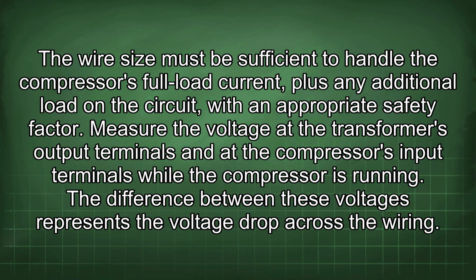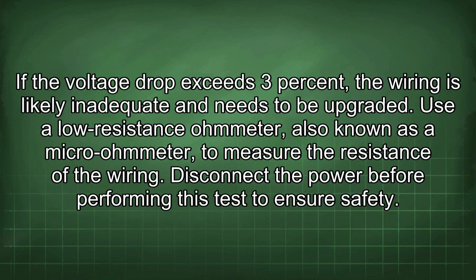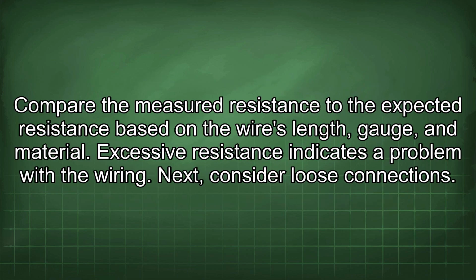Measure the voltage at the transformer's output terminals and at the compressor's input terminals while the compressor is running. The difference between these voltages represents the voltage drop across the wiring. If the voltage drop exceeds 3%, the wiring is likely inadequate and needs to be upgraded. Use a low-resistance ohmmeter, also known as a micro-ohmmeter, to measure the resistance of the wiring. Disconnect the power before performing this test to ensure safety. Compare the measured resistance to the expected resistance based on the wire's length, gauge, and material. Excessive resistance indicates a problem with the wiring.